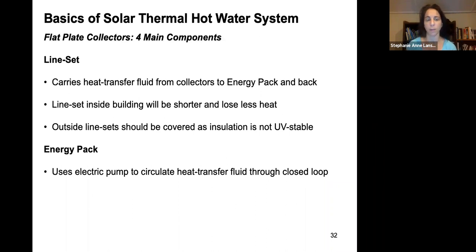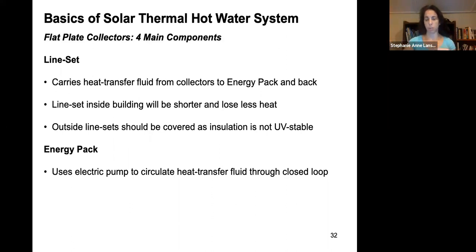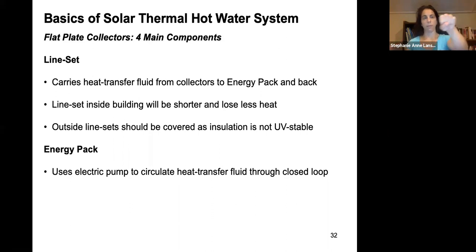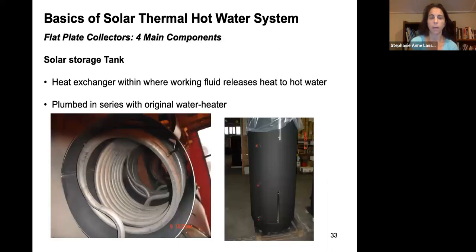After the solar collector, the line set carries the heat transfer fluid from the collectors to the energy pack and back. If the line set is inside a building, it is shorter and loses less heat; if it runs outside for a longer length, it should be insulated to prevent heat loss. The energy pack uses an electric pump to circulate the heat transfer fluid through the closed loop. It is controlled by temperature — when hot enough, the fluid from the collector runs to where it will be used, and the cooled fluid returns to be heated again.